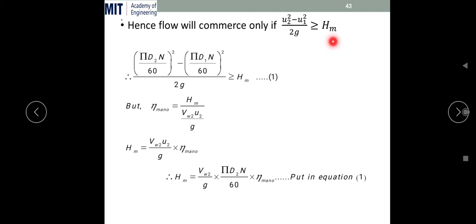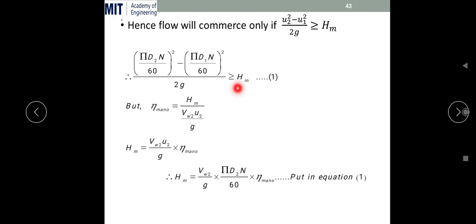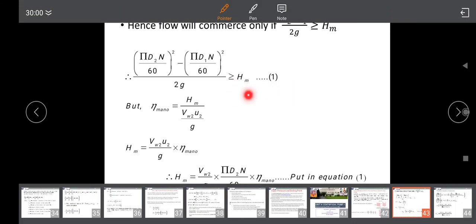We already know that the manometric head is the total head against which the centrifugal pump has to do work. Now put u₂ and u₁ in terms of (πD₂N/60)² minus (πD₁N/60)², divided by 2g, and set it greater than or equal to the manometric head — call this equation number one.